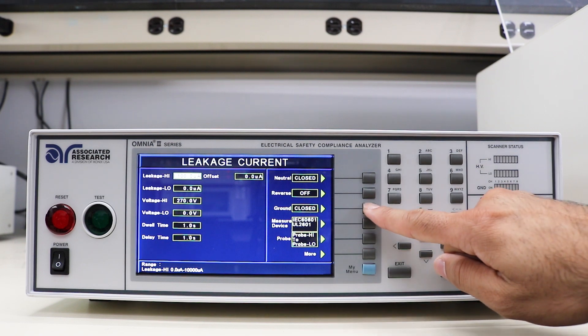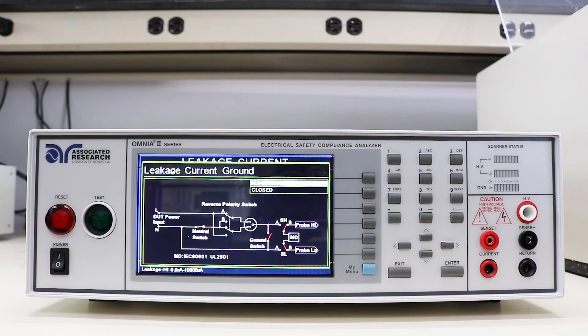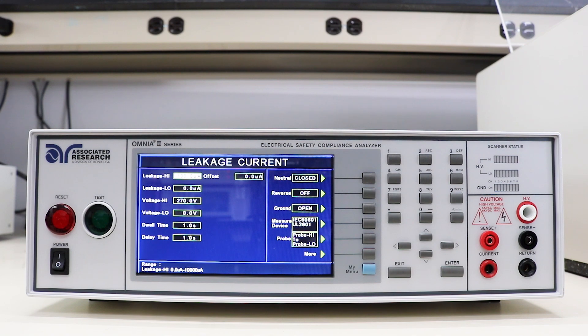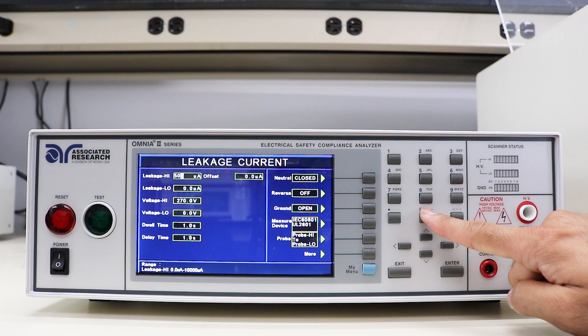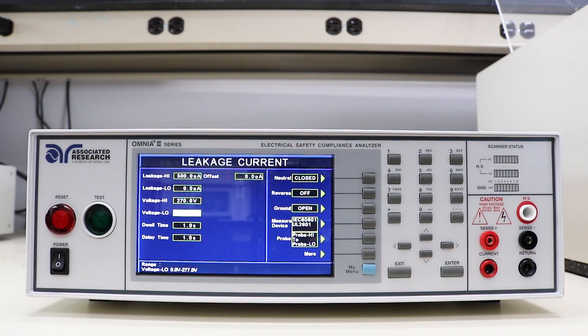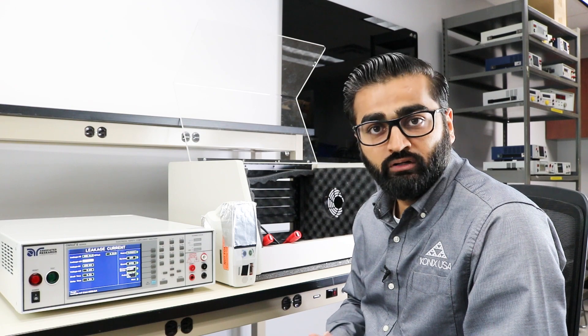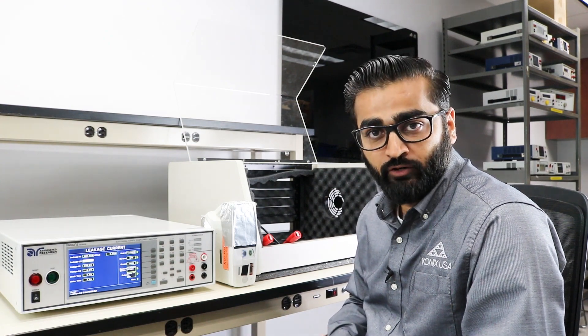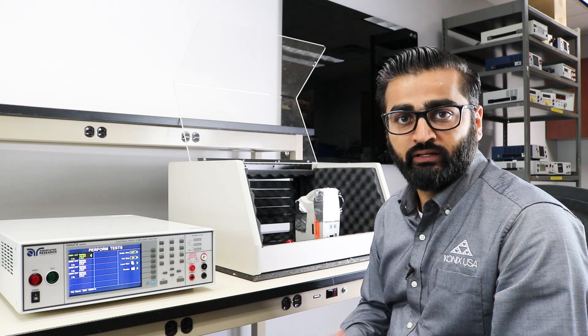Next, we want to make sure we induce one fault condition. In order to induce the fault condition for open ground, we want to select open on the ground relay. For a single fault condition, the standard allows up to 500 microamps of leakage current, so we want to make sure we enter 500 microamps to the leak high limit. Under a normal condition, this limit should be set to 100 microamps. Now let's take a look at all the required test connections for this touch current test.